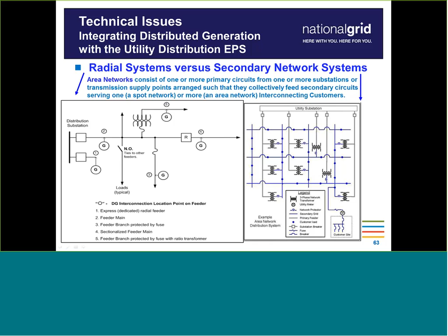So what we're seeing now, I think Tim might have mentioned, is that we're getting to the point of DG saturation on some feeders, even on some substations as a whole. We're backfeeding into the transmission system. And somebody's question, which Tim covered, I do want to elaborate on. It was the one about what level we reach feeder saturation. It depends is my answer for that one. We can upgrade things. We can upgrade the station getaway to be something greater than like 556 spacer cable, but at that point, one, it's probably non-standard construction, but two, you're getting to the extremes of the equipment right there, and that's a point where it gets really expensive.